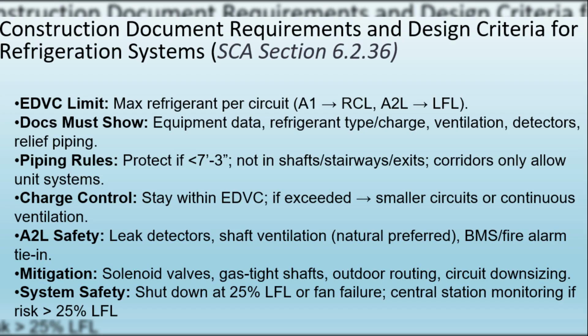Both A1 and A2L systems must meet EDVC charge limits, and if exceeded, designers must either break the system into smaller circuits or add continuous ventilation. For A2L piping, continuous ventilation is the preferred option. Designers must size ventilation airflow properly using ASHRAE formulas. In many cases, leak detectors and interlocks with the fire alarm system are required. Shafts carrying refrigerant piping must be ventilated, either naturally or mechanically, with natural ventilation being preferred.